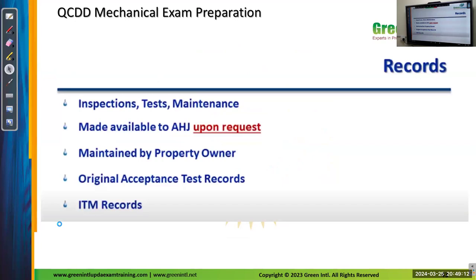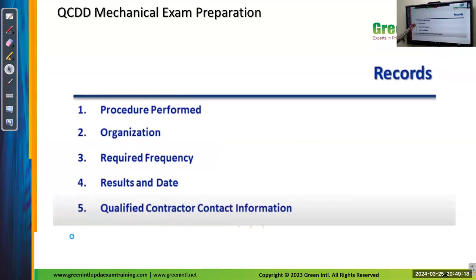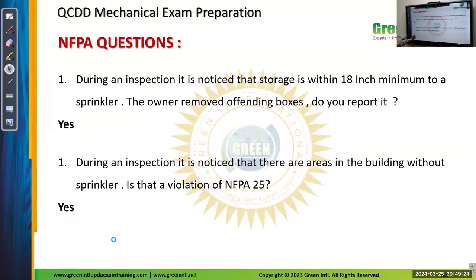So inspection, testing, and maintenance records must be made available. These are all the records we have to maintain: procedure performed, organization that performed it, required frequency, test date, who conducted this inspection. Some questions: during an inspection, it is noticed that storage is within the 18-inch minimum clearance to a sprinkler. The owner removed the offending boxes. Do you report it?